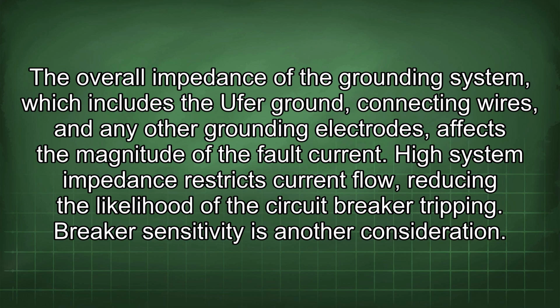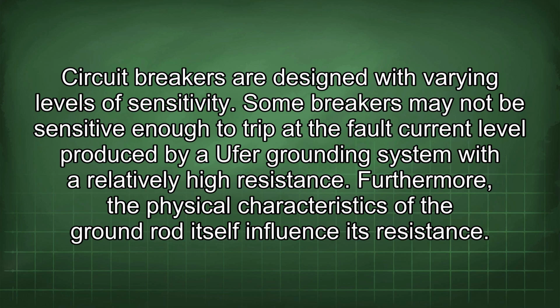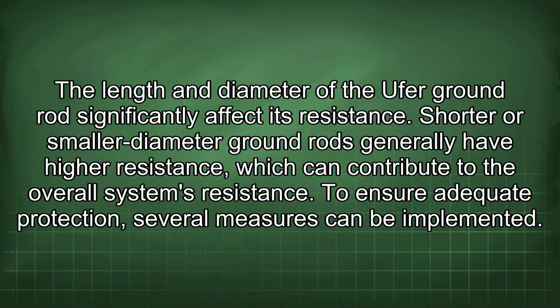Breaker sensitivity is another consideration. Circuit breakers are designed with varying levels of sensitivity. Some breakers may not be sensitive enough to trip at the fault current level produced by a Ufer grounding system with a relatively high resistance. Furthermore, the physical characteristics of the ground rod itself influence its resistance. The length and diameter of the Ufer ground rod significantly affect its resistance. Shorter or smaller diameter ground rods generally have higher resistance, which can contribute to the overall system's resistance.